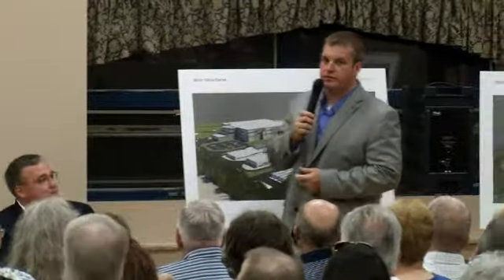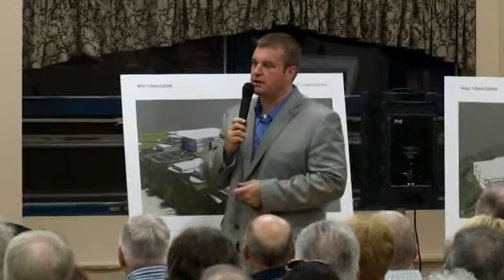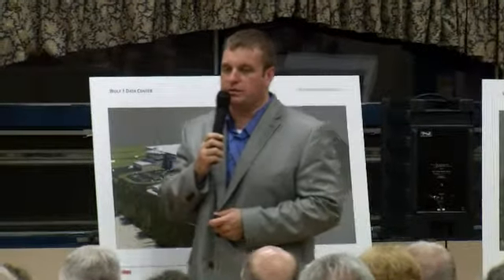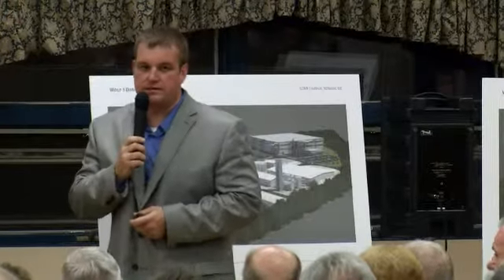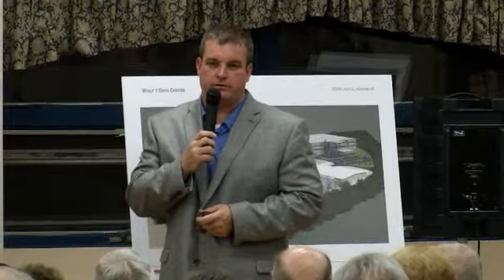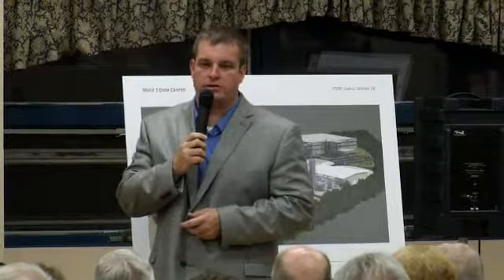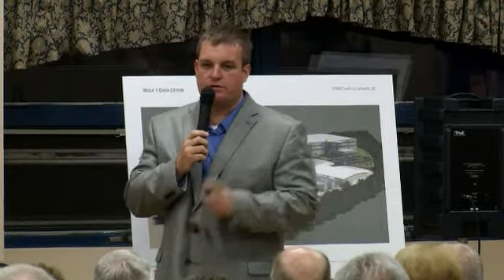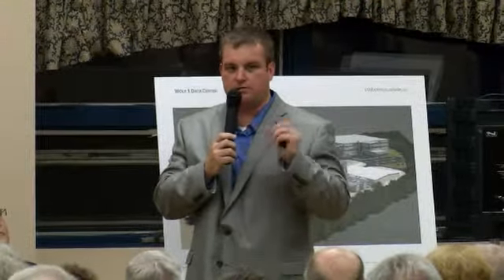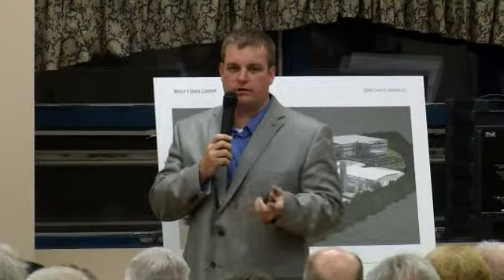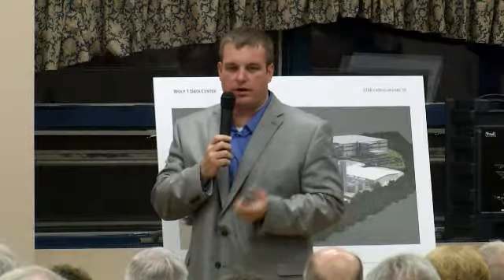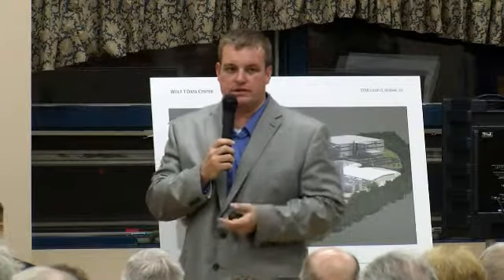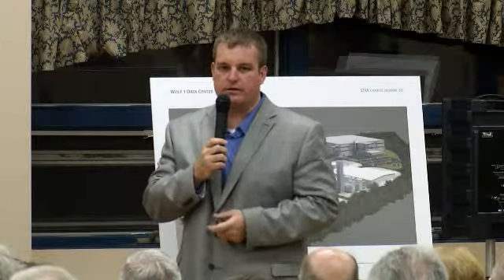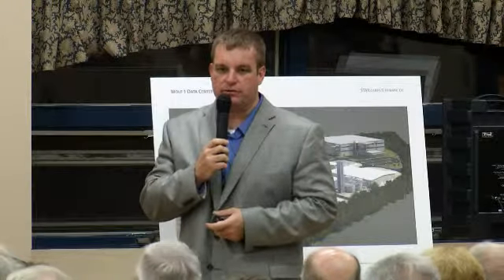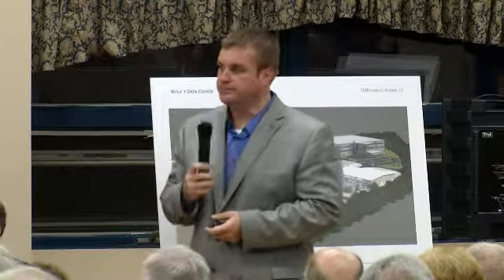Another clear distinction is the difference in design between a typical power plant and our design for the data center. A power plant would drop in one or two very large generators, connect them to a single gas supply, and let them spin to generate power. We're installing multiple units for redundancy, as discussed earlier, to supply power to our data center and to provide redundancy for the power and the cooling.